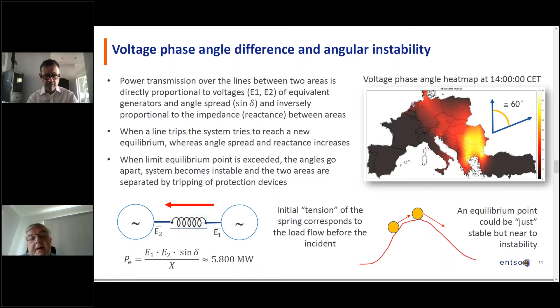Starting where the split happens. You also see here the frequencies: on the one side the frequency went down very quickly, on the other side the frequency went up very quickly, because the split happens at the maximum exchange, and so this complete exchange is interrupted, meaning that in the southeastern parts of Europe there is 5,900 megawatts too much generation compared to loads, and in the northwest part there is 5,000 megawatts too much load compared to generation. And so immediately the frequency reacts because this high load or this high generation has to be compensated with kinetic energy of the running machines. So the frequency goes up very quickly in the Balkan area and goes down very quickly in the rest of Europe.